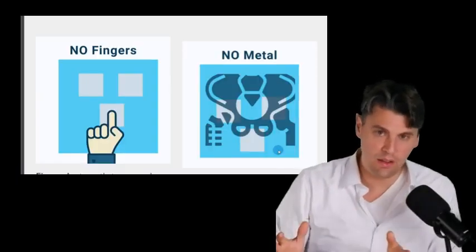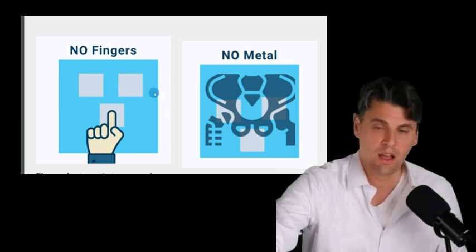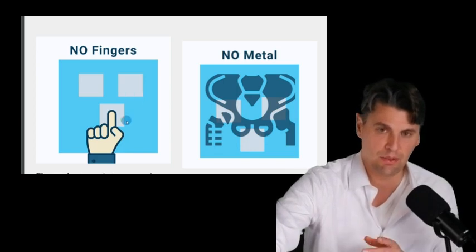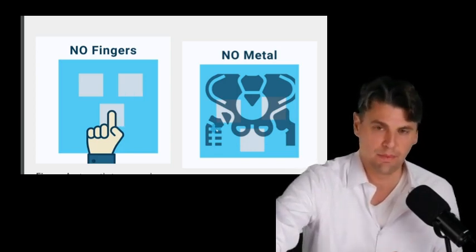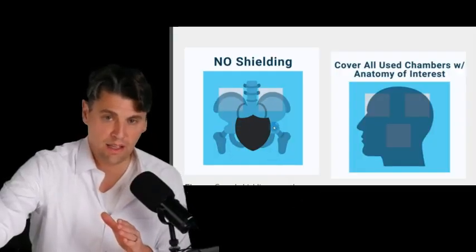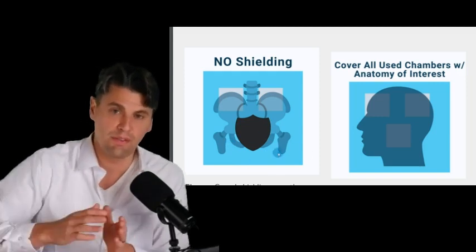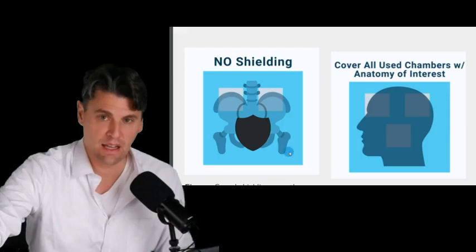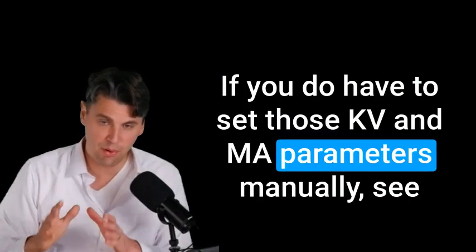In our AEC video, we go through all the details. On the outside of your system, you can actually see where those chambers are. And you want to make sure your anatomy is completely contained within those chambers. So don't try and image a little finger that's only going to take out part of the chamber. And don't put a piece of metal in there because you're going to get a spurious reading. Also, don't use gonad shielding in AEC. Gonad shielding is something we have separate video on, which is really phasing out in radiography in modern times.